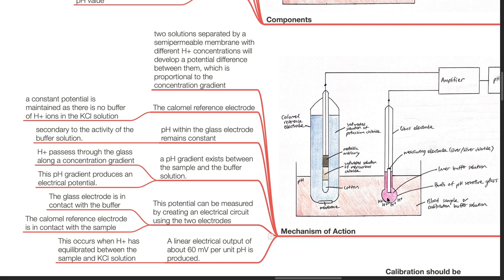A pH gradient exists between the sample and the buffer solution. Hydrogen ions pass through the glass along a concentration gradient. This pH gradient produces an electrical potential, which can be measured by creating an electrical circuit using the two electrodes. The glass electrode is in contact with the buffer, whereas the calomel reference electrode is in contact with the sample. A linear electrical output of about 60 millivolts per unit pH is produced when hydrogen ions have equilibrated between the sample and the potassium chloride solution.